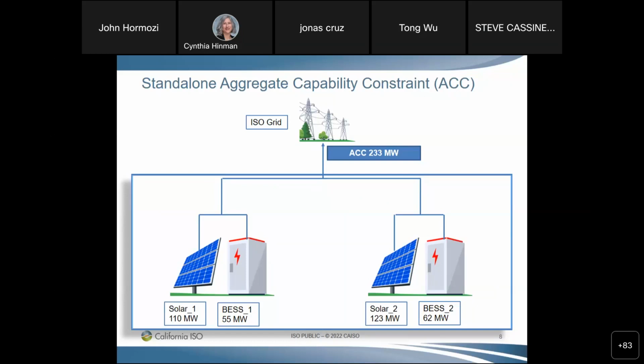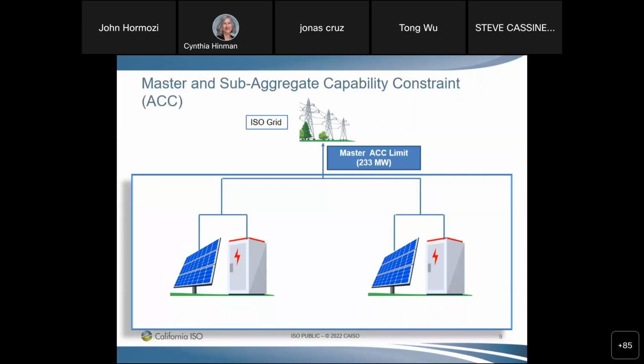An ACC was set up to ensure that no more than 233 megawatts could be dispatched for any combination of these resources at once. Now there's another situation where there is an ACC at the point of interconnection, but with additional contractual limitations related to how these resources can be dispatched. In this case, the scheduling coordinator might want to set up a master ACC with subordinate ACCs—we call that master and sub ACC. Let's take a look at an example of that.